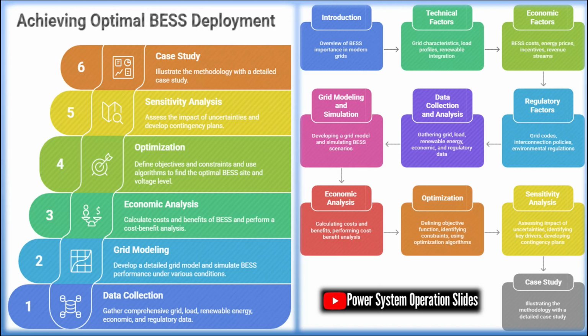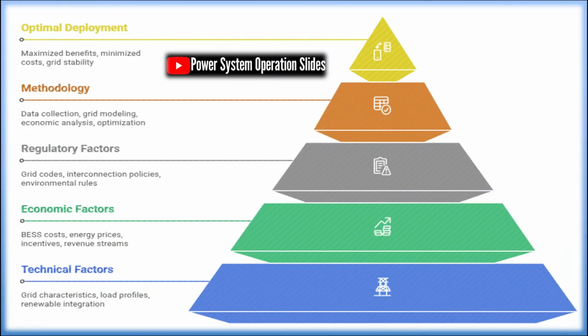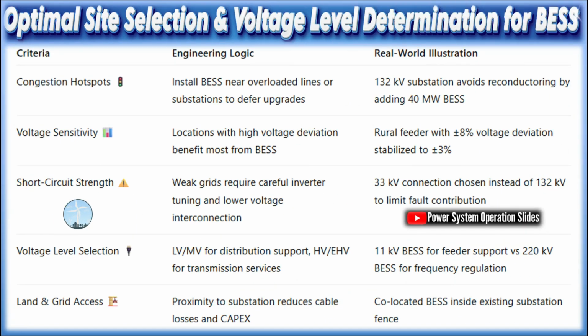Distribution-level BESS facilities are typically located at the end of distribution feeders where voltage drop problems are most pronounced, in urban load pockets where demand is concentrated, or in areas with high rooftop PV penetration where reverse power flow issues can occur. The voltage level selection rule of thumb is relatively straightforward. Fast system services such as frequency regulation and congestion relief are best provided at higher voltage levels where the BESS can quickly inject or absorb large amounts of power, while local power quality issues such as voltage regulation and loss reduction are most effectively addressed at lower voltage levels closer to the affected loads.